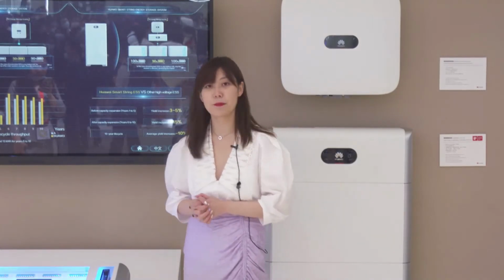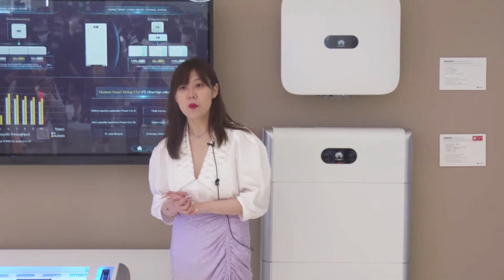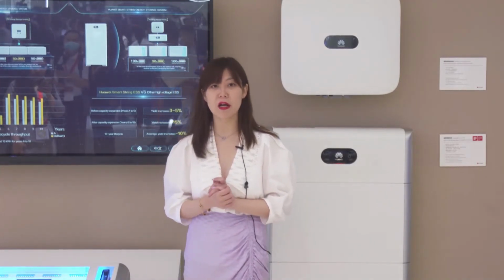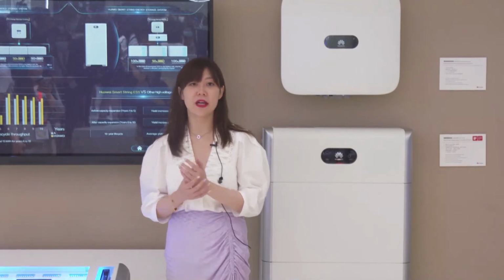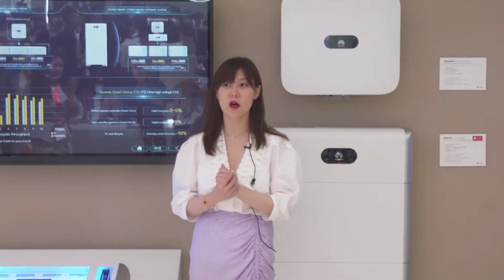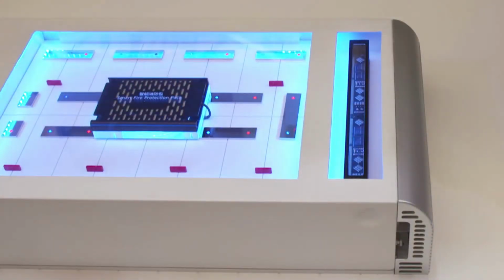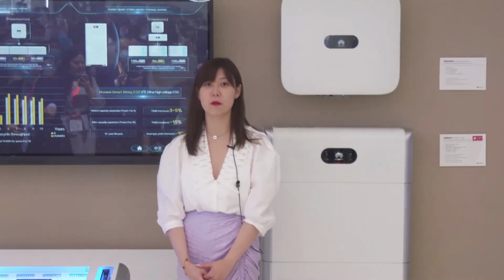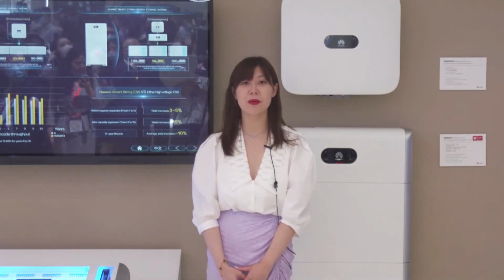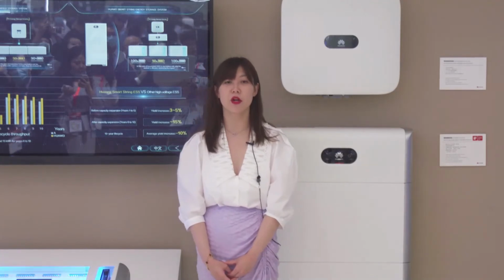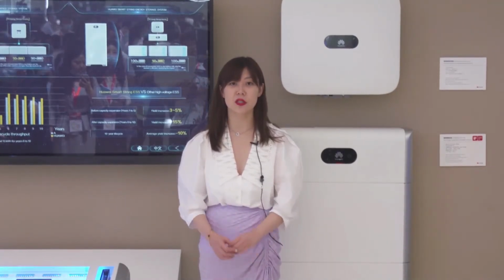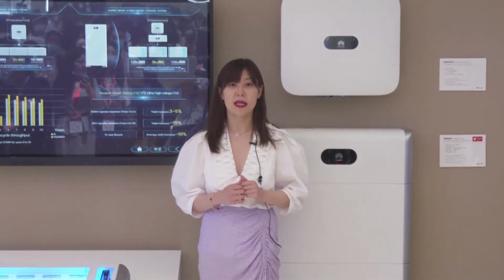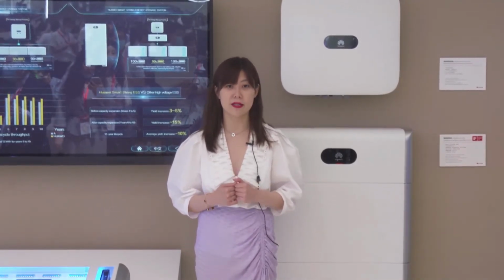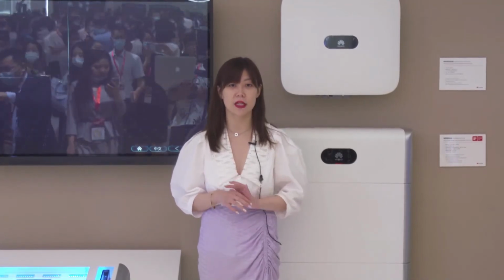Another focus of the battery is safety. We noticed some battery providers in the market had explosion and fire accidents recently, and their products were recalled. But Huawei Smart String ESS can achieve end-to-end safety protection. It has zero voltage at ports for safe operation, and also cell-level monitoring in real time. Cloud-based BMS and AI-enabled health monitoring can identify short circuits in just 20 seconds and disconnect them in 1 ms, covering the bursts and derivatives of internal short circuits.